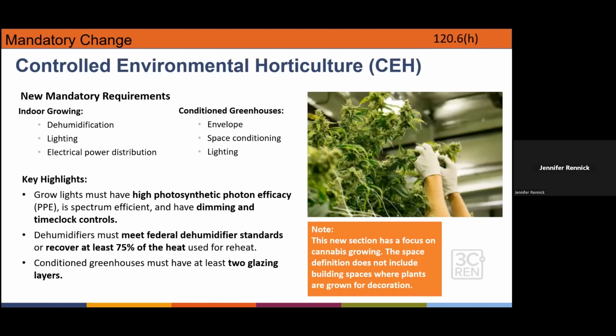And for the controlled environmental horticulture, CEH spaces, this was specifically targeted for cannabis growing, and not greenhouses where you're growing decorative plants. There are some new mandatory requirements on efficiencies, and a couple of the key highlights are that the grow lights have to have a special type of high spectrum efficiency with dimming and timeclock controls, and the dehumidifiers have to meet special federal dehumidifier standards now. And if you're doing a conditioned greenhouse, the glazing system has to have at least 2 layers, be dual paned essentially, or dual plastic glazed.